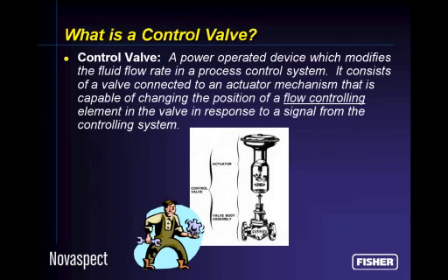A basic definition to get us all grounded in terminology: a control valve is a power-operated device which modifies the fluid flow rate in a process control system. It consists of a valve connected to an actuation mechanism that is capable of changing the position of a flow controlling element in the valve in response to a signal from the controlling system. You see the components there of the control valve. We'll talk more about these in detail, but what's important to know is that the control valve itself does not control pressure. It does not control temperature, conductivity, pH. It controls flow, and as a result of controlling flow, it controls the measured variable that you need to have on set point.